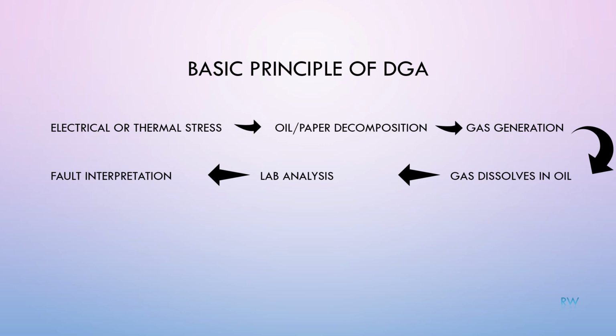The principle is simple. Electrical or thermal stress causes decomposition of oil or paper insulation. This decomposition produces gases. The gases dissolve in transformer oil. Oil samples are taken and analyzed in the laboratory. The measured gas values are then interpreted to identify fault types.